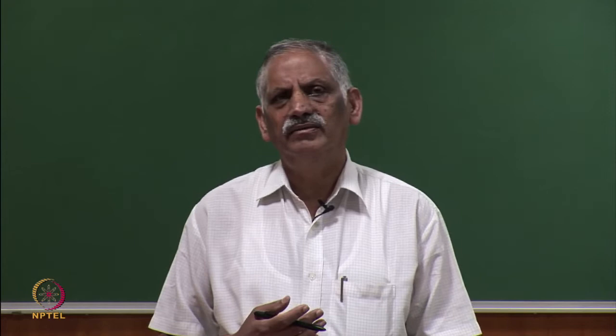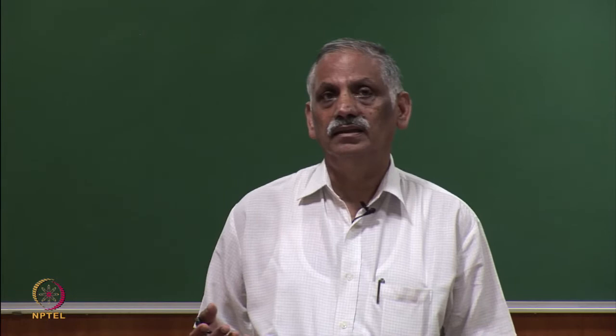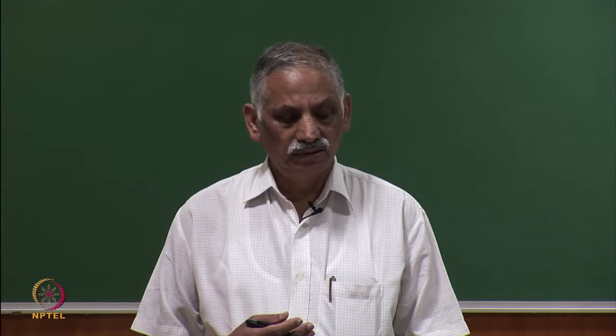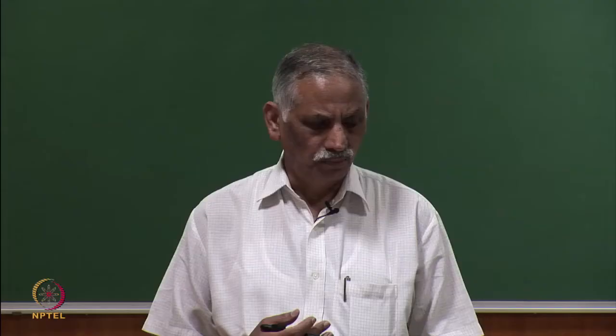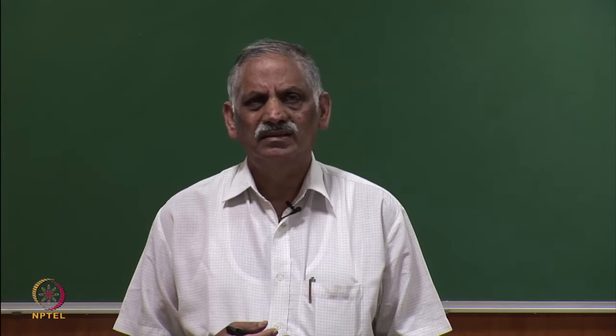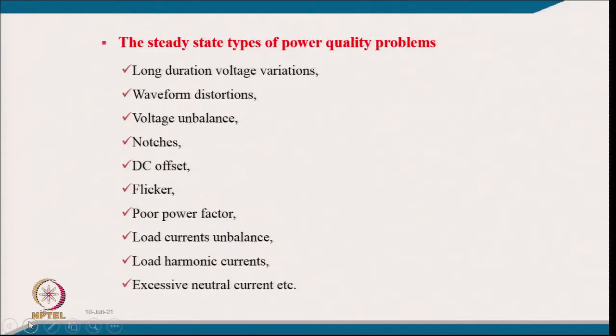Voltage imbalance causes increased heating and losses in induction motors and other loads. Notches in voltage, DC offset — where some load draws a small DC current causing issues in transformers, AC equipment, and inductors — and flicker are other steady-state problems. Flicker from welding and similar loads causes irritation. Poor power factor and load current unbalance cause unbalanced voltage at the point of common coupling.